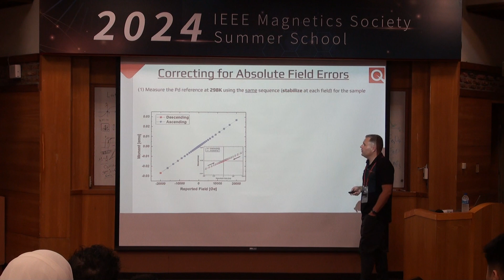So all we need to do is calculate the true field by dividing that measured moment by this quantity here, the susceptibility, and we tell you the mass of the palladium reference sample. And again, we know the susceptibility at 298 Kelvin very well. This is just obviously a screenshot from Origin here. And we can calculate the true field based on this measurement of the magnetic moment. Now, all we need to do in post-processing is take this column here and replace it here, and I'll show you how that's done. So this again is our loop with this problem here, this inverted loop, replacing the reported field with the calculated true field, and we get a hysteresis loop that now makes sense again.